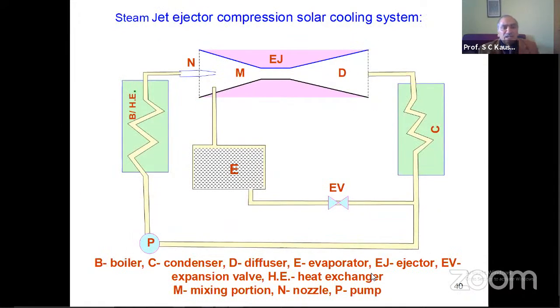Now, as I mentioned, the steam jet ejector cooling system is another option, where we replace the mechanical compressor by an ejector compression system. It is some kind of thermocompression. It is a converging-diverging nozzle, where at the inlet a nozzle is there and at the outlet we have a diffuser. The diffuser behaves like a compressor and the nozzle behaves like an expander.